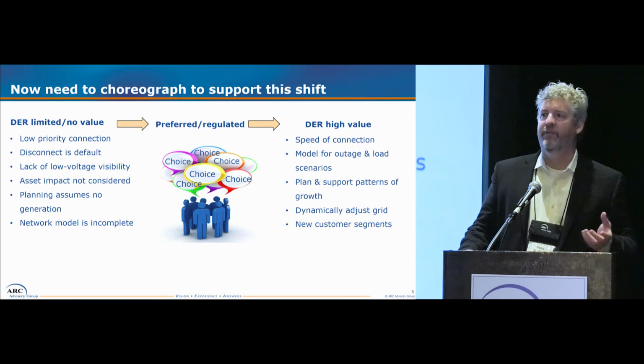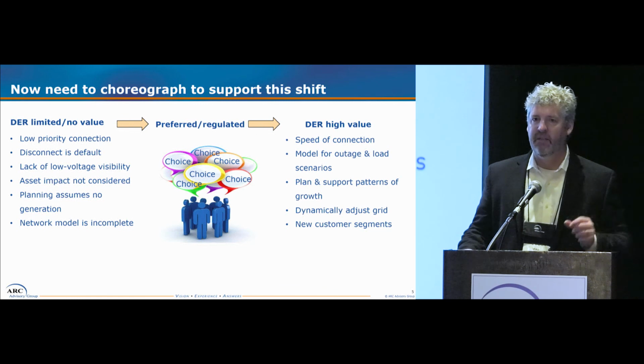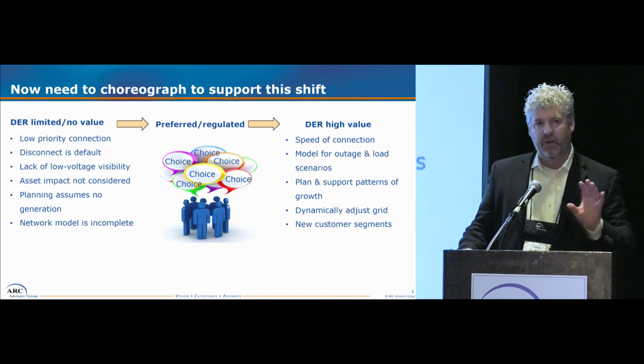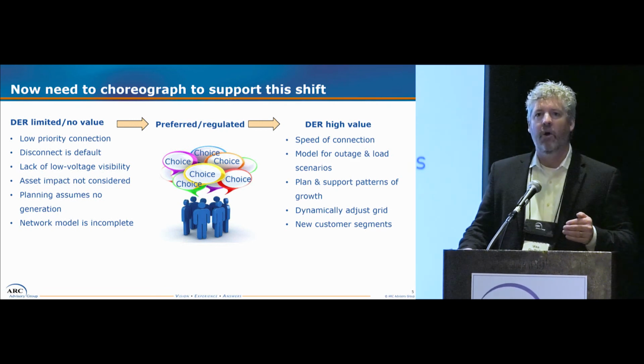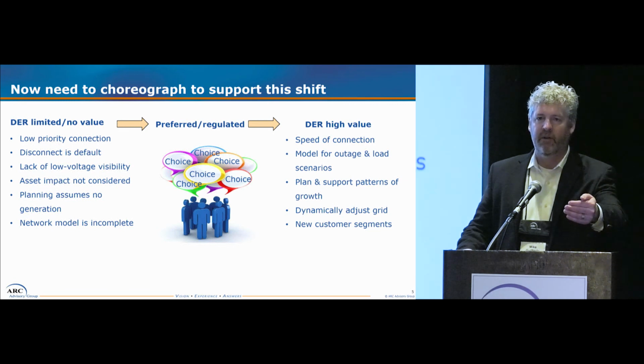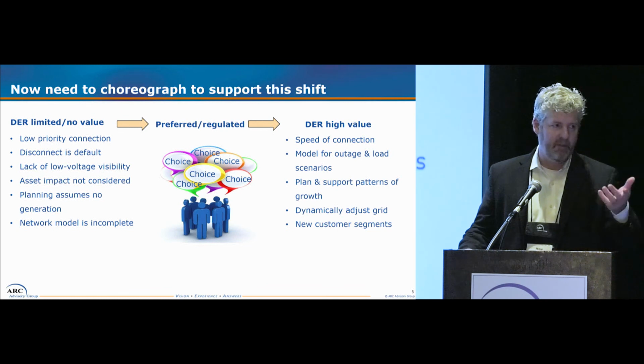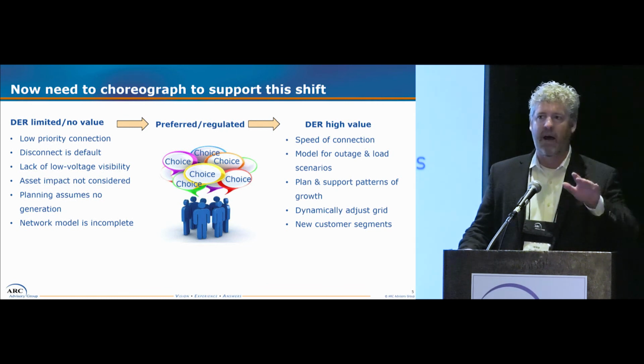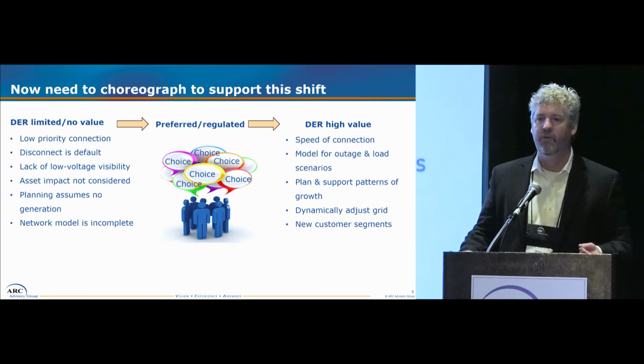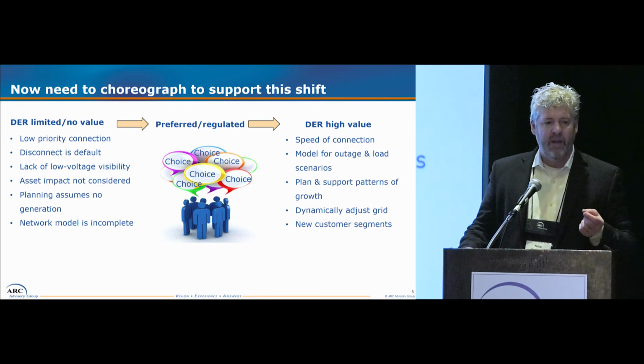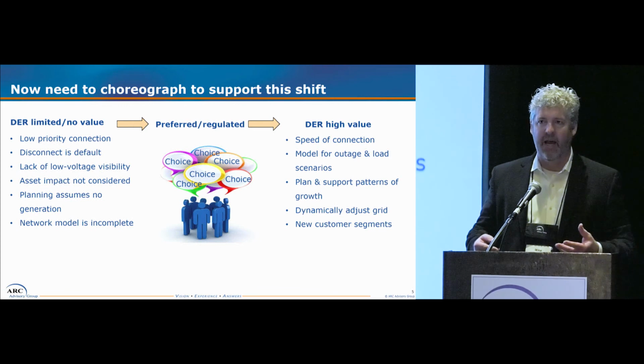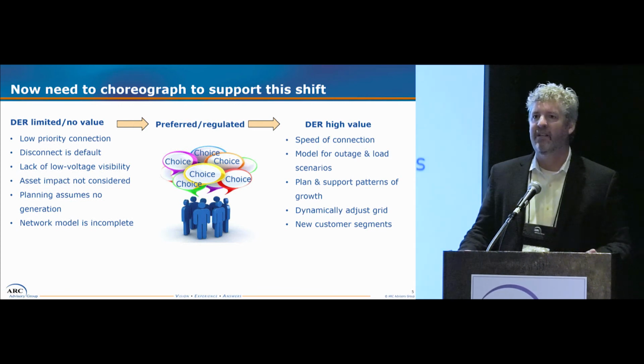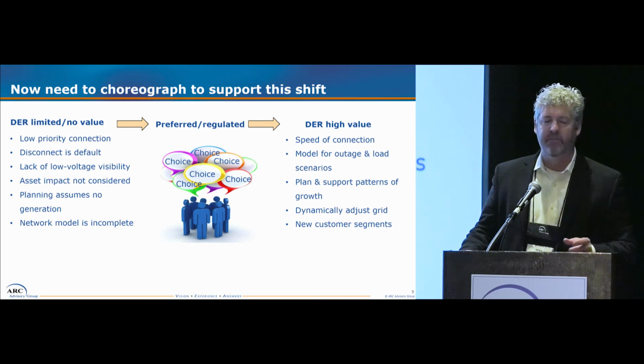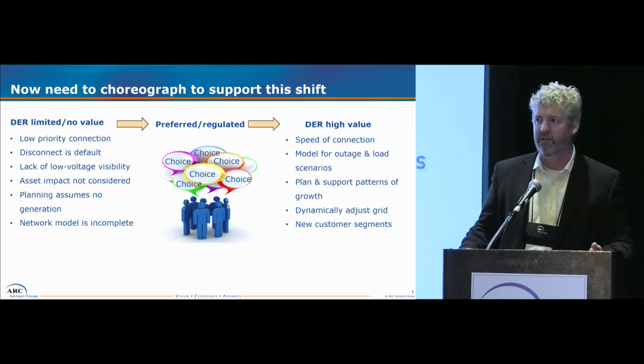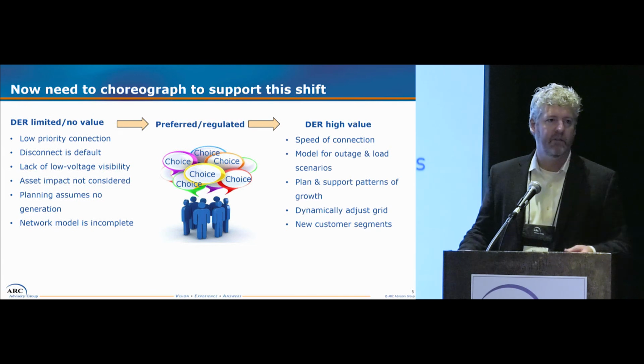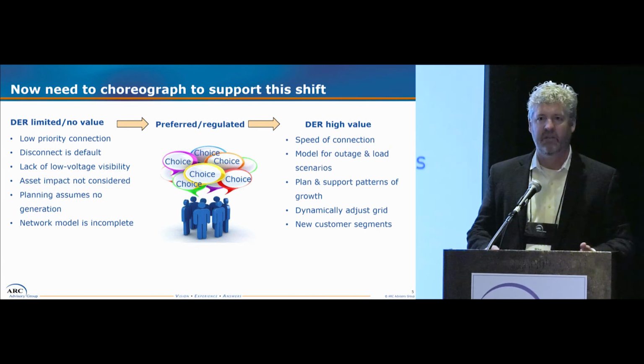There was also a lack of low voltage visibility, and this is really important because it addresses something fundamental that Dwayne's going to talk about today. Because of that centralized structure, the utilities only needed to go so far out into their grid in terms of visibility, typically at the substation, maybe a little beyond in terms of transformers. But they stopped the tendrils of visibility at some point because they didn't need to worry about individual points on the grid. So when they looked at reliability planning and capital investment, they just didn't consider those distributed resources as part of their planning, investment, or operational processes, such as inrush after an outage. They simply didn't consider them because they never had to.